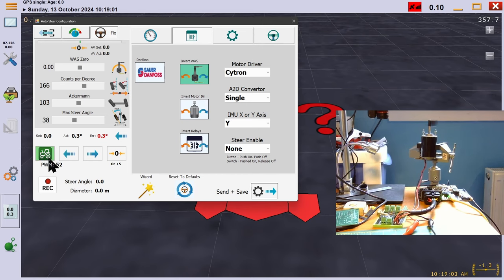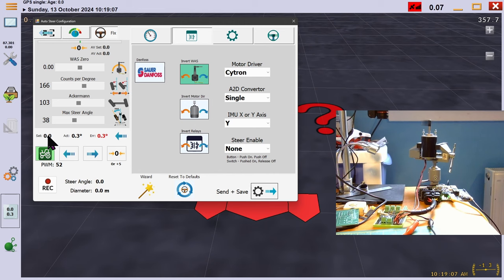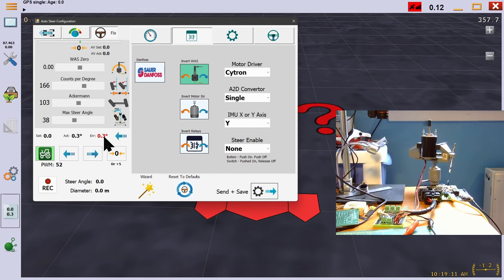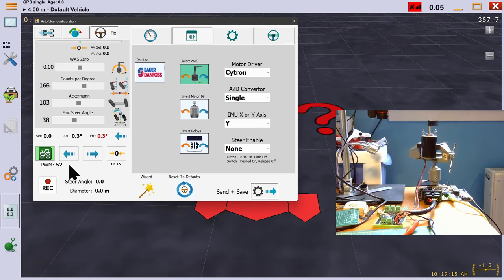Now we engage drive again and with a set angle below 0 and the actual at 0.3, we can see the motor is turning very fast. If we only needed to steer that minor correction, it would be bad turning the wheel so fast.